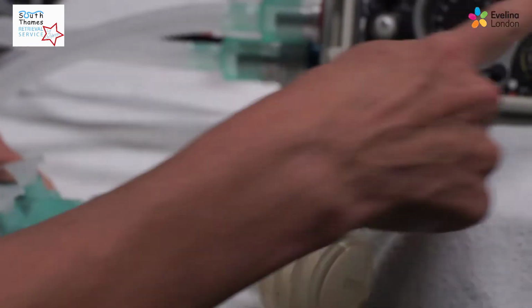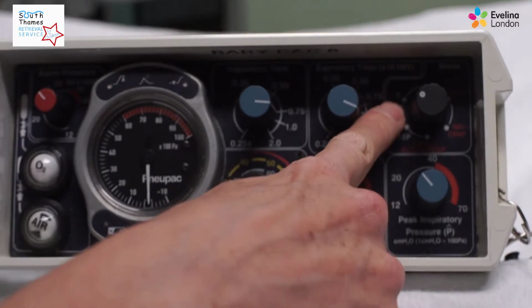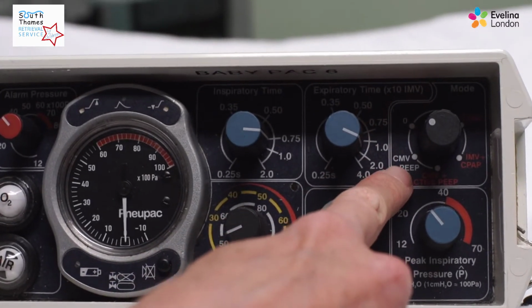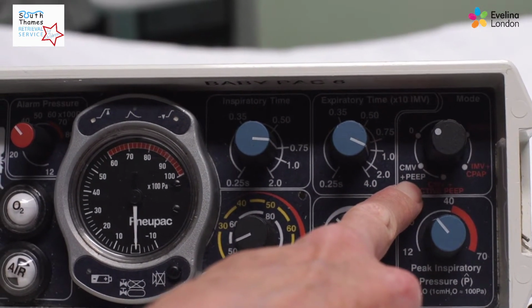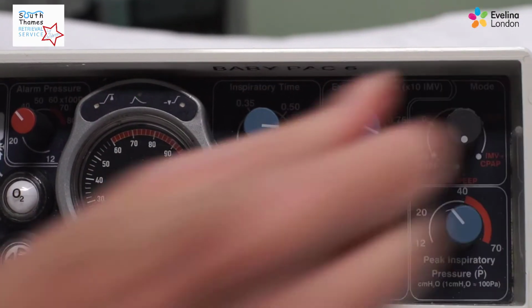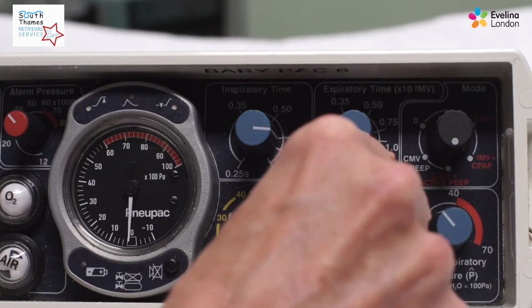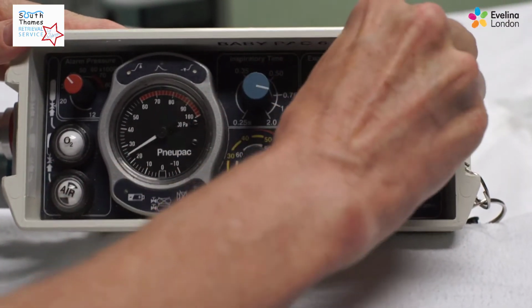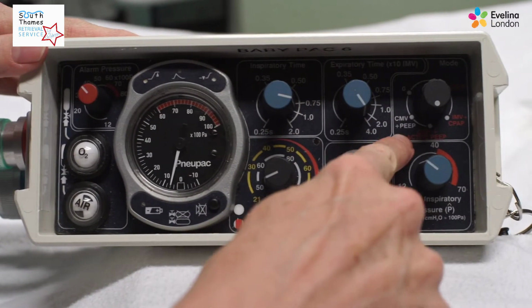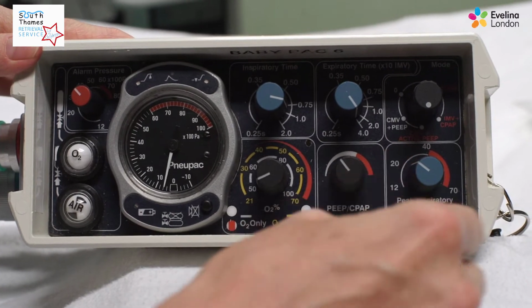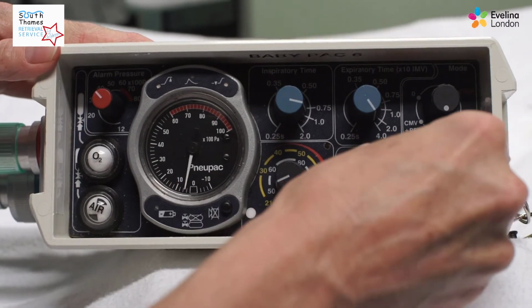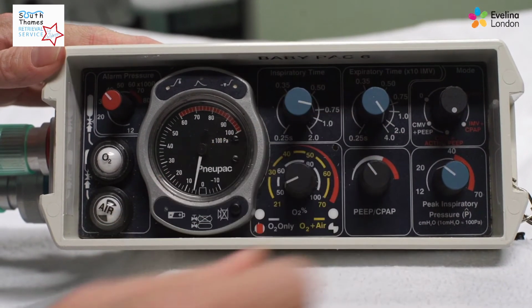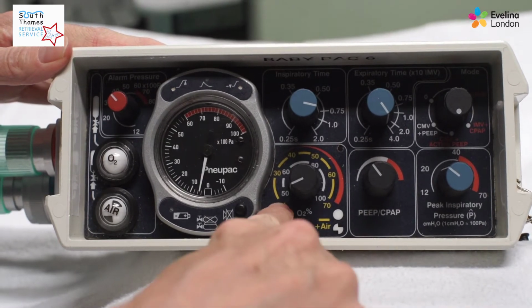Then I'll be using a false lung to test the ventilator. 0 is off. CMV with PEEP will give you PEEP, but it's not continuous. We tend to favour CMV with active PEEP. We're going to turn the ventilator onto CMV and active PEEP. At the moment, we're delivering 21% oxygen. We have a PEEP reading of about 4 and a peak pressure of about 24.